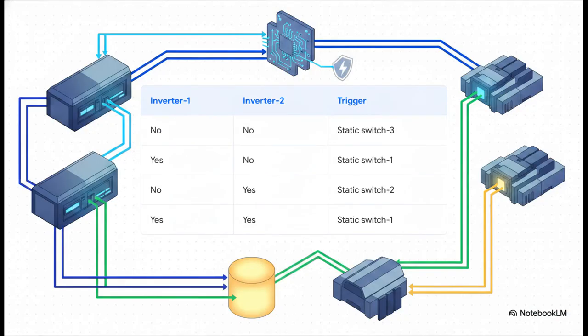Here's that fail-safe brain actually doing its thing. The microcontroller constantly monitors the system using a logic table. If inverter 1 is healthy, it routes power straight through static switch 1. If inverter 1 fails but inverter 2 is healthy, boom, it instantly triggers switch 2. Now, if both inverters completely fail, the logic table tells it to immediately trigger switch 3, which pulls power from a bypass constant voltage transformer. It's just this rapid-fire decision matrix, making sure the signal always has power.